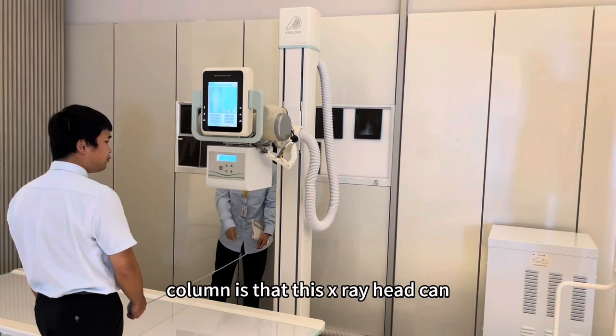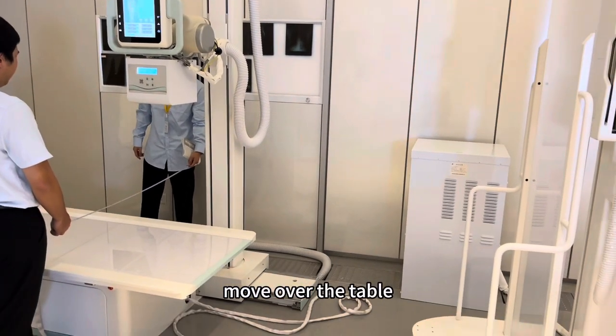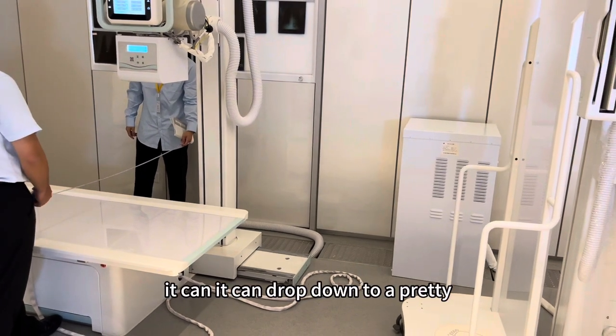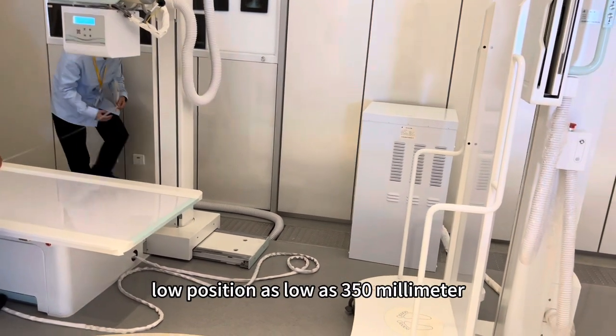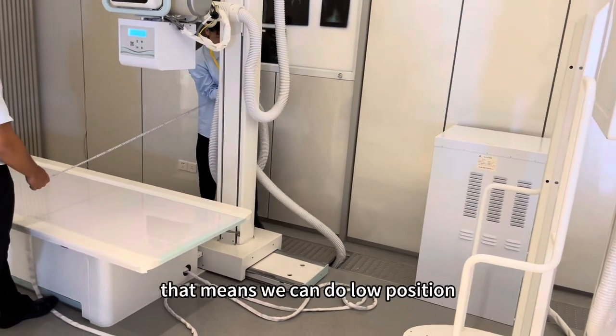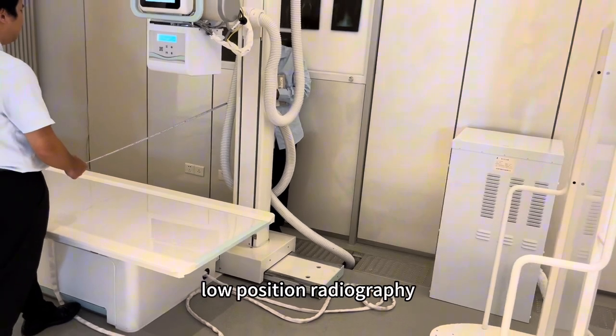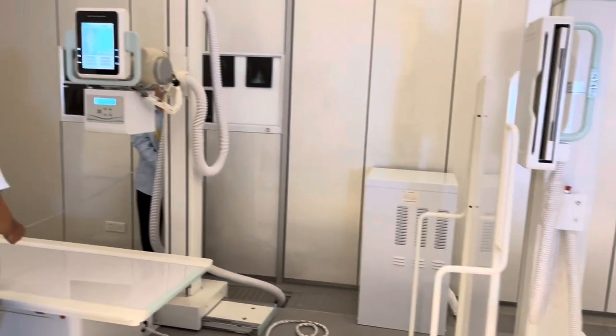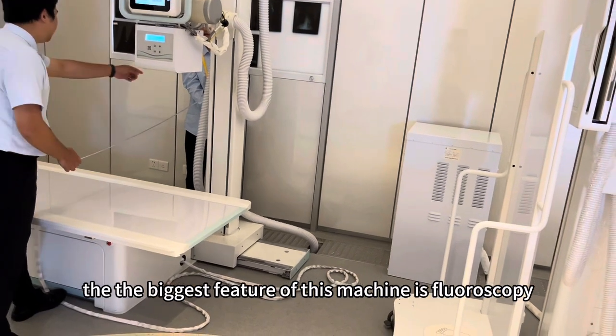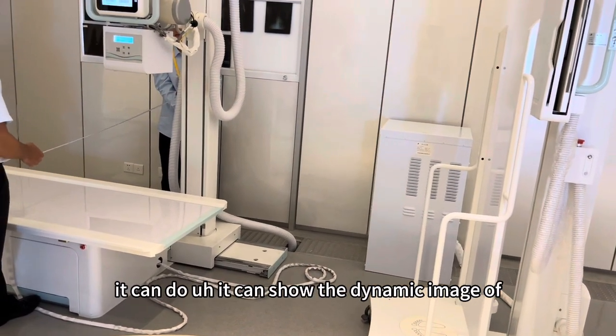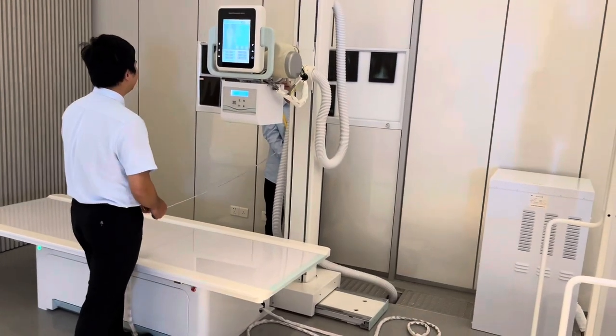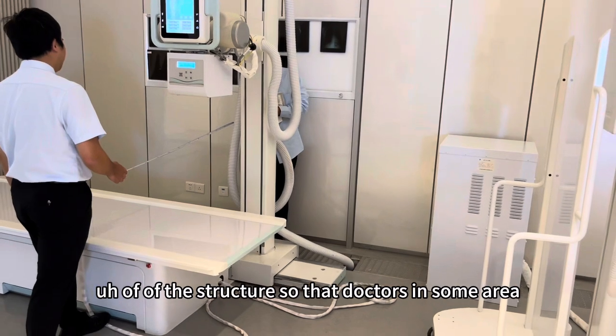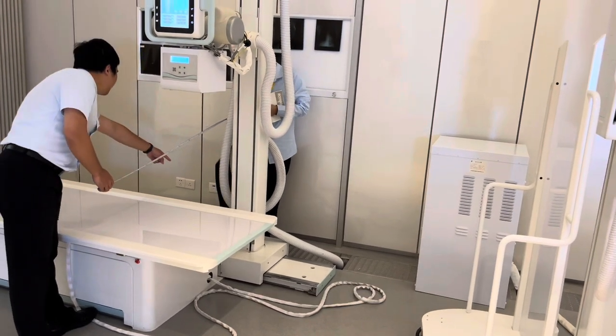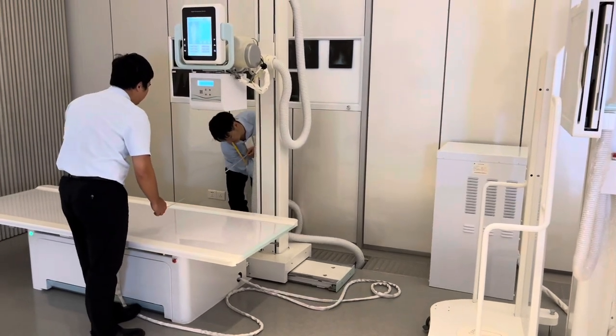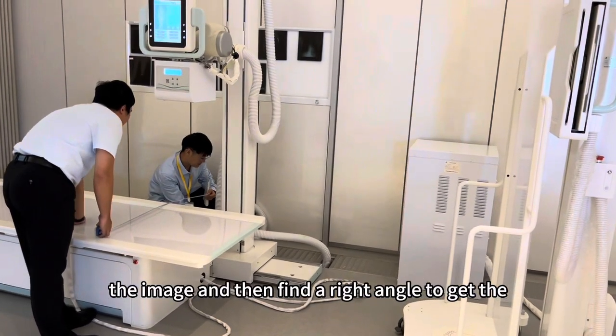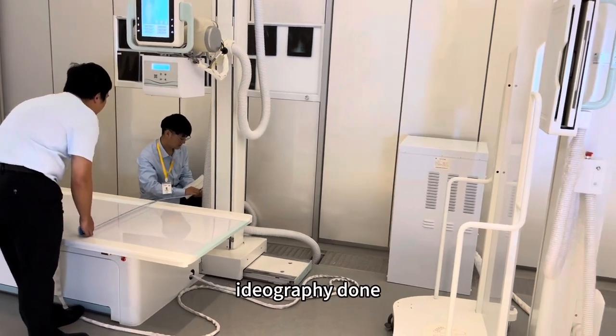And this collimator, this X-ray head can move over the table. It can drop down to a pretty low position, as low as 350 millimeter. That means we can do low position radiography. And the biggest feature of this machine is fluoroscopy. It can show the dynamic image of the structure, so that in some scenarios doctors can preview the image and then find a right angle to get the radiography done.